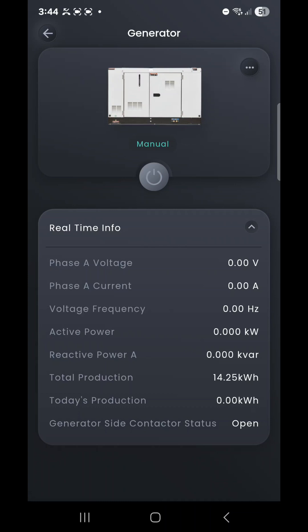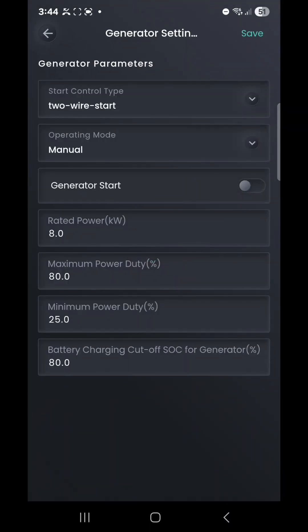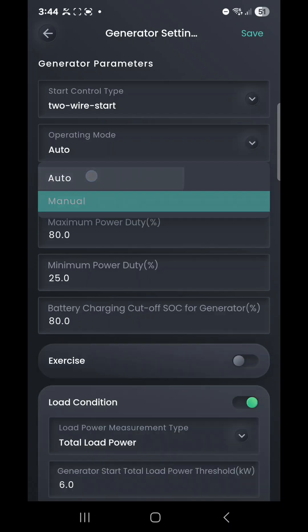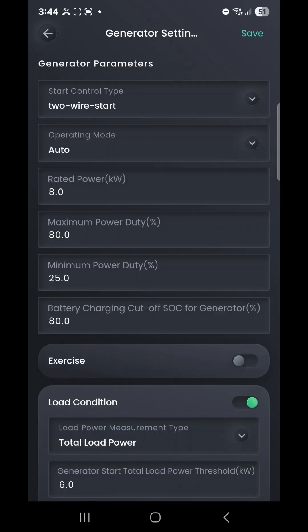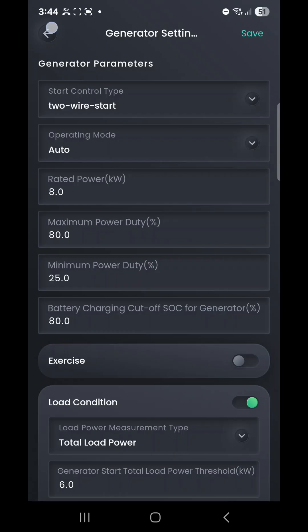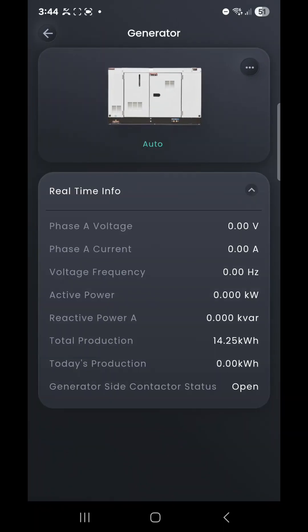It's really important once you do a force charge on your battery system that you remember to go up into your settings on the three dots on the top right-hand side, go back to operating mode, and simply hit Auto, then hit Save. If we go back now to our generator with that top back left button, it'll be back on automatic start mode. That's a really important step—to always remember to hit Save before you return so it actually takes that setting on board.